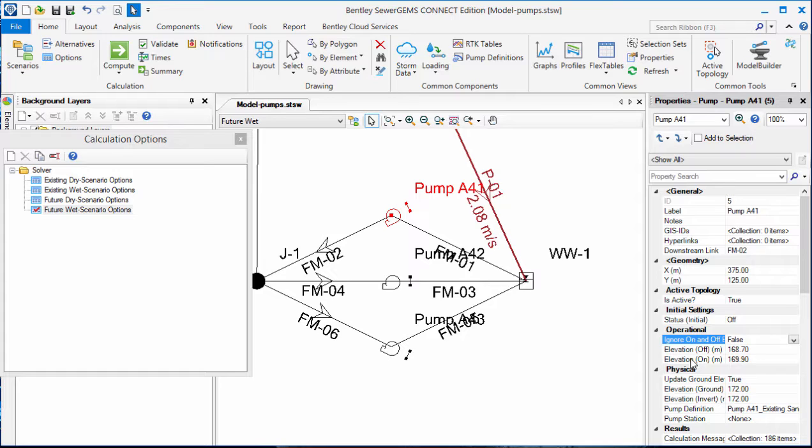However, when the model is computed, there's a large deviation of results in the wet well. You can see this if you graph the results. You can also use the hydraulic reviewer to show the volume of water coming into the wet well versus what's coming out of the wet well.